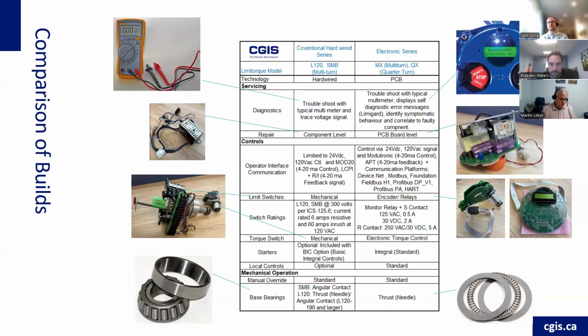The SMB uses angular contact bearings. These angular contact roller bearings were designed for very high thrust and to minimize or mitigate any side loads. You'll see these on sluice gates, heavy equipment, hydroelectric dams, and similar applications where they're lifting heavy loads. The newer, more competitive actuators, the L120s, use a needle bearing style, which is very good, and more economically designed for the application. Both actuators are designed for longevity in the application they're designed for.